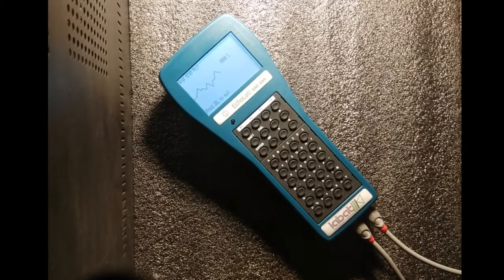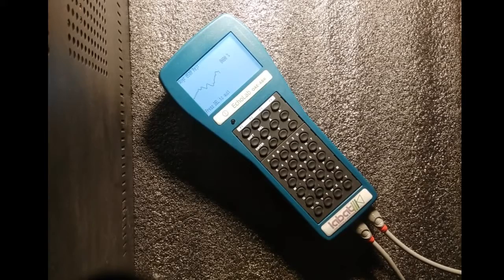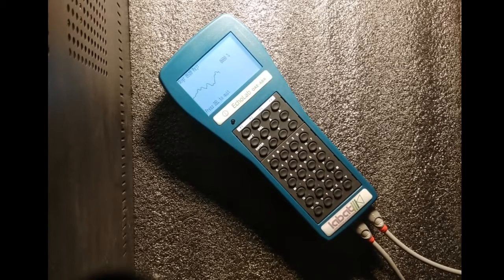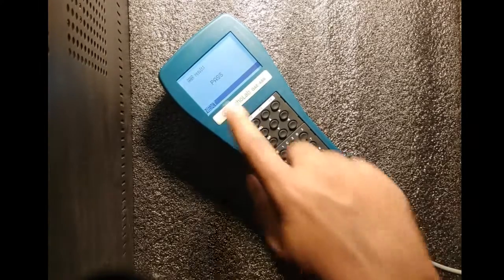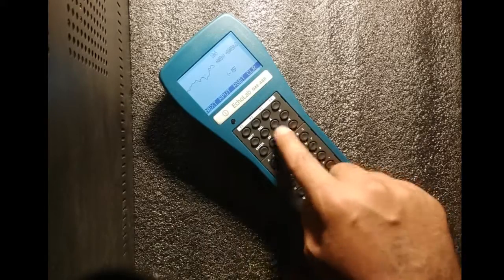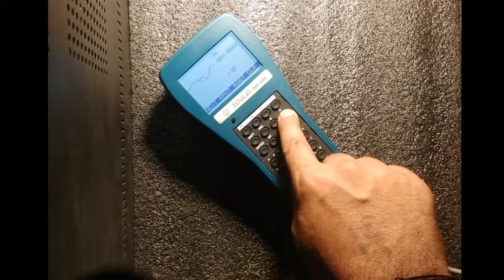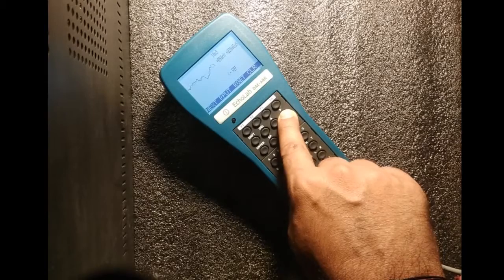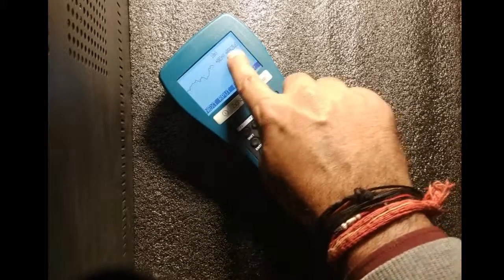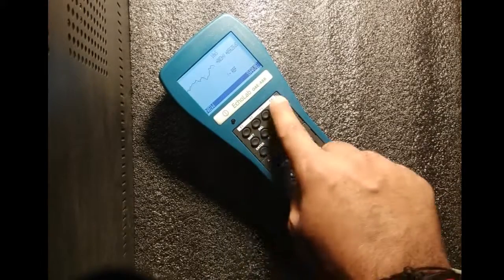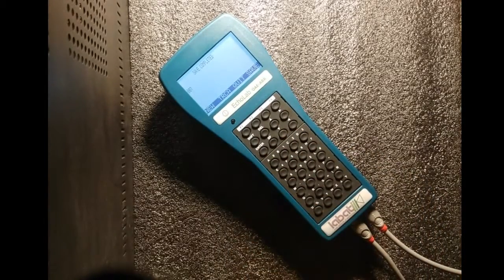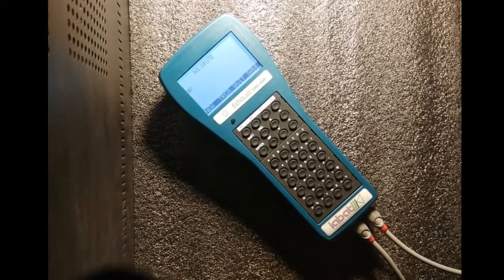Now it is showing the pass result. I'm pressing next and it is showing me the waveform. You can use these arrow marks to check the peak values. You can see it is showing the time over here. Now you can hit next and then save the test, and later on you can import the test from the equipment to the PC.